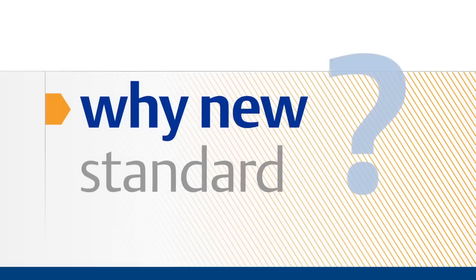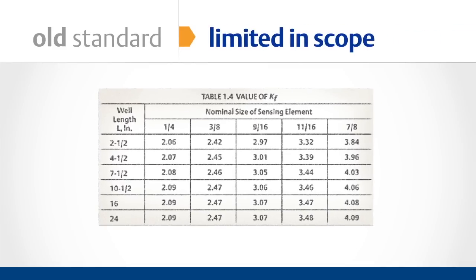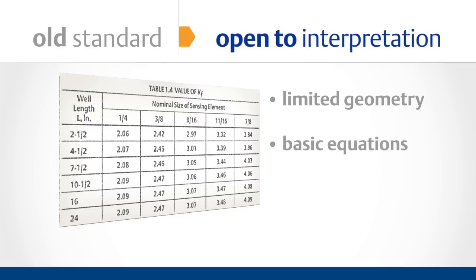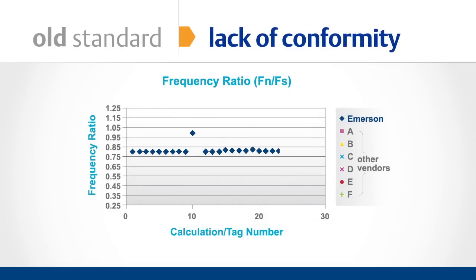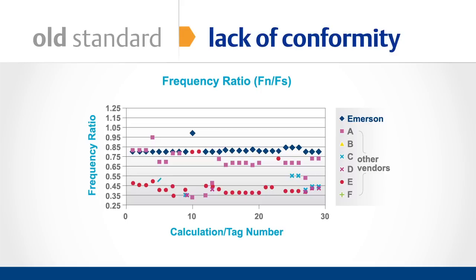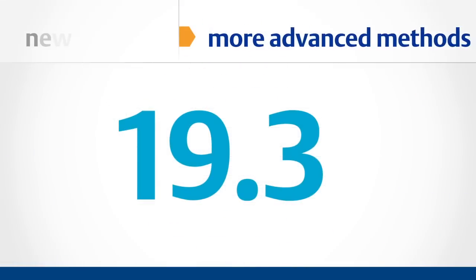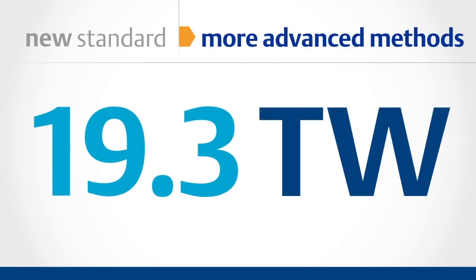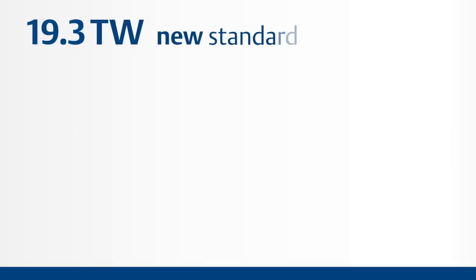It's important to understand why a new standard was needed. The old standard was very limited in scope and overly simplistic. As a result, the standard was open to interpretation. This is what Emerson Process Management found when comparing our frequency ratio results with those of several other vendors — they all claimed to conform to PTC 19.3, yet you can see significant variance in the results. In addition, more advanced methods such as finite element analysis, along with experimental results, caused many in the industry to move away from a strict reading of test code 19.3. Clearly, a broader and more reliable standard was needed.